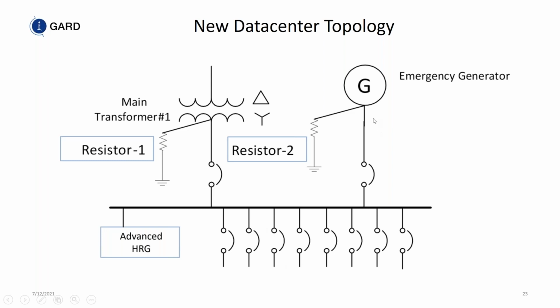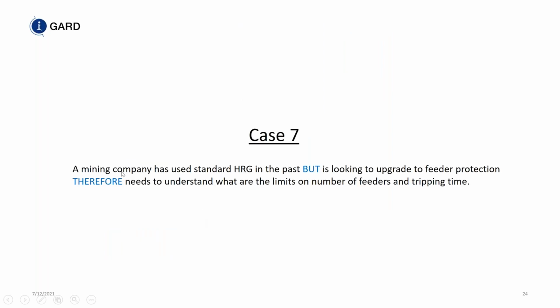We do monitor the voltage on the bus between the generator and the ground and the load, and between the transformer and the load. So you can still tell if there's a fault in the system, even though we're not monitoring the current. Typically, most of our competitors cannot do this. Case number 7. A mining company has used standard high resistance ground in the past, but is looking to upgrade the feeder protection, therefore needs to understand what are the limitations on the number of feeders.